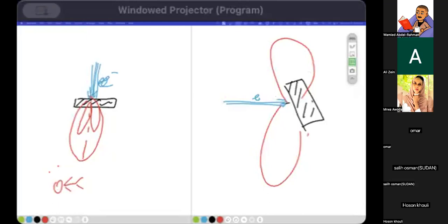When the electron gun is changed, one of the QAs that you do is the flatness and symmetry. And also the output. You see the energy, how much this energy is penetrative. But actually your calibration could be off, by the way. I think that's the big problem. So changing it, you need to recalibrate the machine.